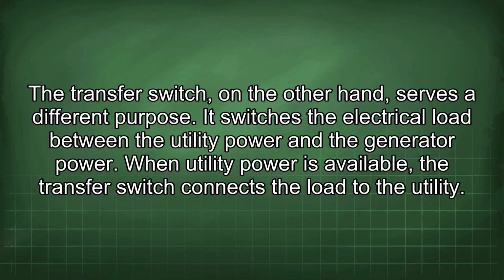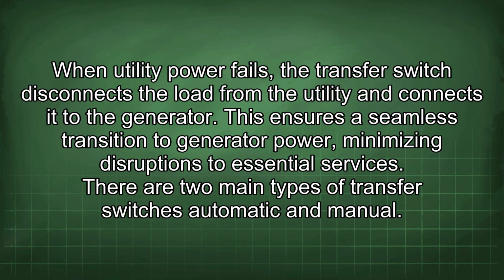The transfer switch, on the other hand, serves a different purpose. It switches the electrical load between the utility power and the generator power. When utility power is available, the transfer switch connects the load to the utility. When utility power fails, the transfer switch disconnects the load from the utility and connects it to the generator. This ensures a seamless transition to generator power, minimizing disruptions to essential services.